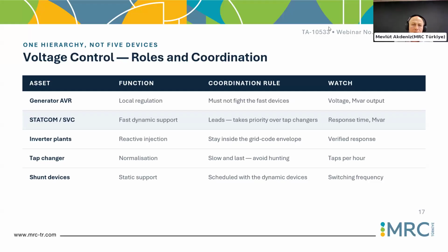So inverter plants are PVs or wind power plants. They are coupled to the grid through inverter structures, and if it is specified in the grid codes or in the technical specification, they can also simulate a similar contribution to synchronous generators, but it should be specified and tested during commissioning in the real practical case on site.